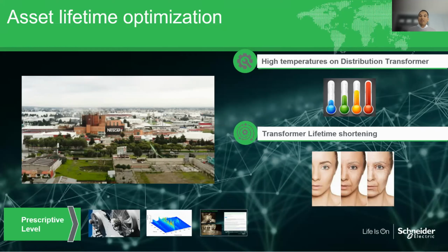This was the case for this particular transformer. So we advised the customer to take different actions. We said you might want to check that the forced ventilation fans are operating to lower the temperature, given that the substation design makes it hard to lower ambient temperature otherwise — that's a much bigger problem to solve. So let's at least check that your fans are working.